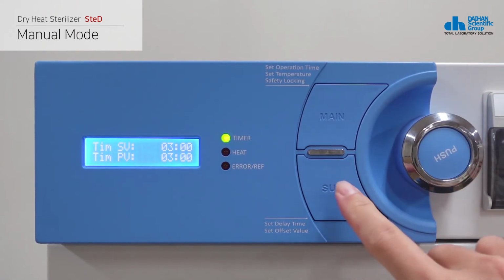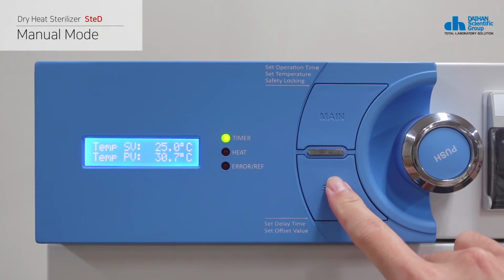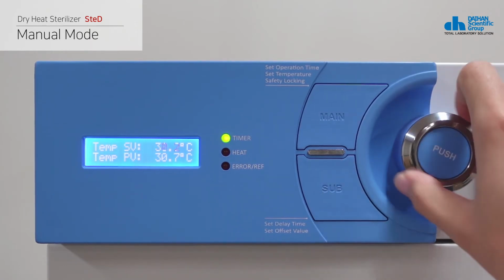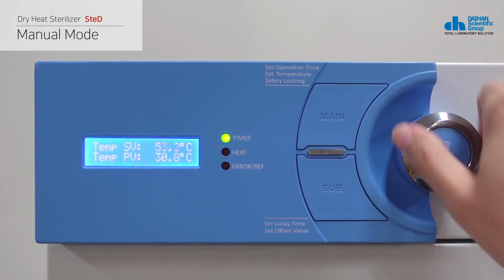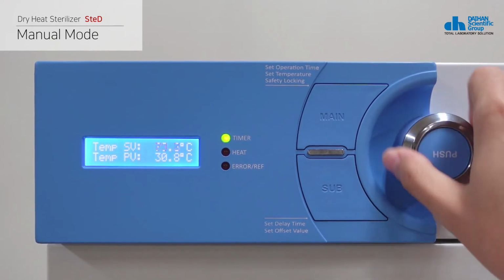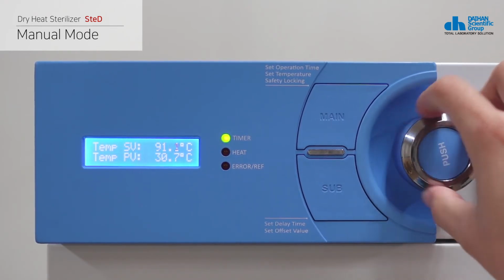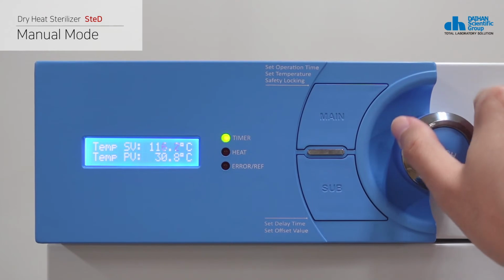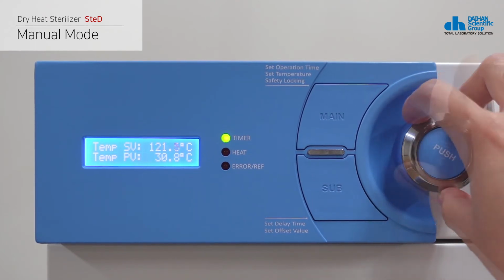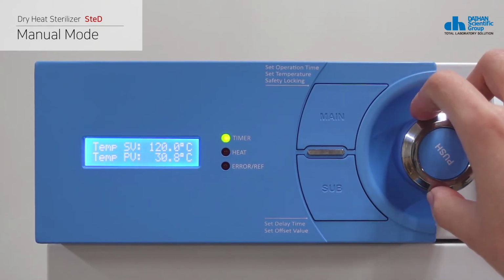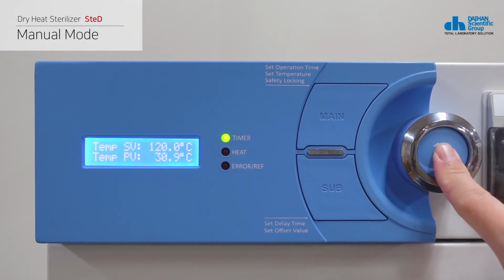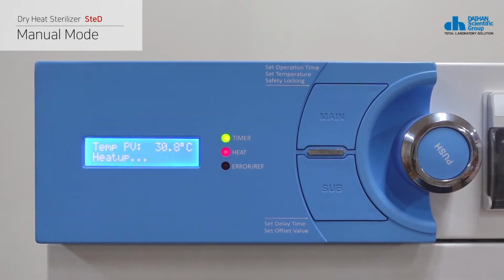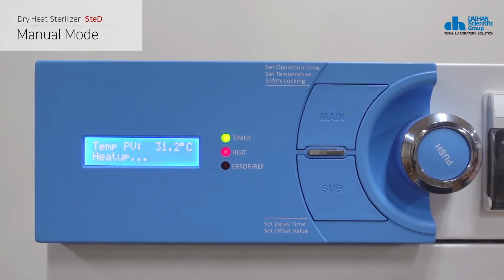Press the sub button in timer setting mode to enter temperature setting mode. In the temperature setting mode, turn the knob to set from 35 degrees Celsius to 230 degrees Celsius in steps of 1 degree Celsius. Press the push button after the setting is completed to start the heating operation. When the heating operation starts, the heat LED on the right side of the LCD indicates whether the heater is operating.